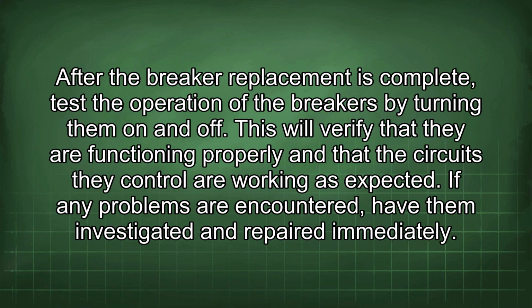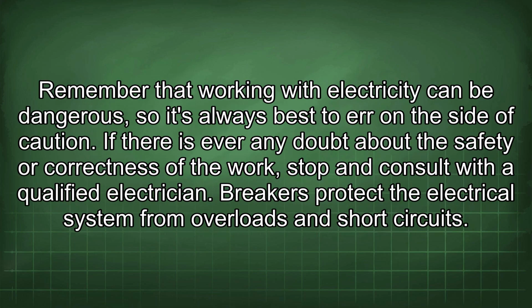After the breaker replacement is complete, test the operation of the breakers by turning them on and off. This will verify that they are functioning properly and that the circuits they control are working as expected. If any problems are encountered, have them investigated and repaired immediately. Remember that working with electricity can be dangerous, so it's always best to err on the side of caution.